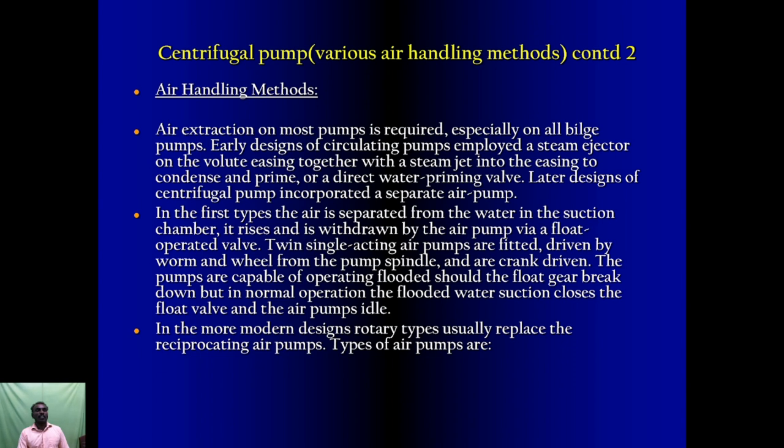Later designs of centrifugal pump incorporated a separator, in which air is separated from the water in the suction chamber. It rises and is withdrawn by the air pump via a float operated valve. Twin single-acting air pumps are fitted, driven by the worm and worm wheel from the pump spindle, and are crank driven. The pumps are capable of operating flooded. Should the float gear break down, but in normal operation, the flooded water suction closes the float valve and the air pump idles. In the more modern designs, rotary types usually replace the reciprocating air pumps.